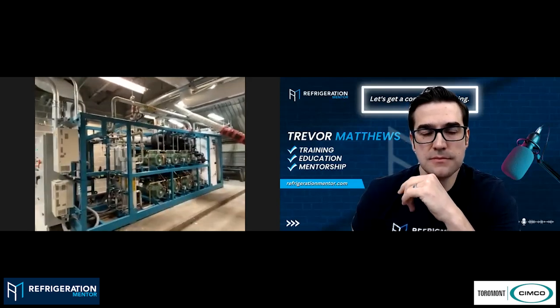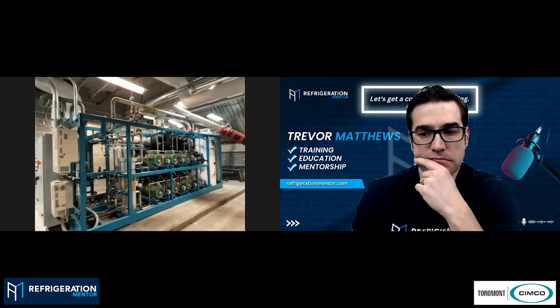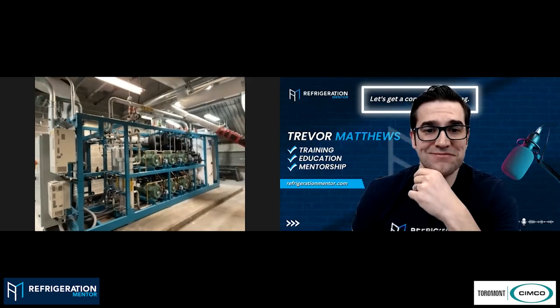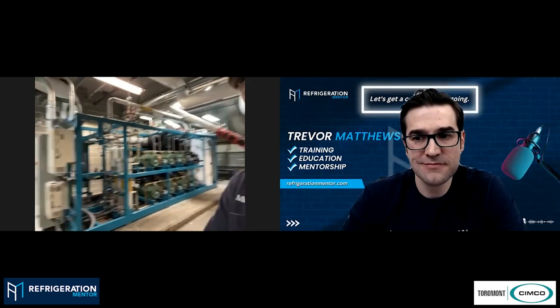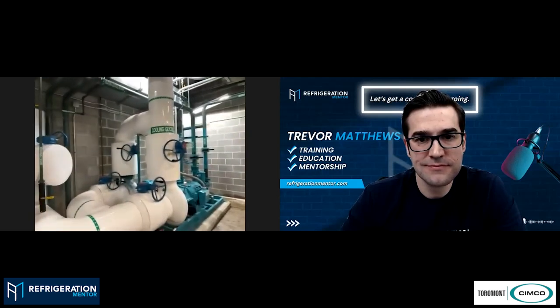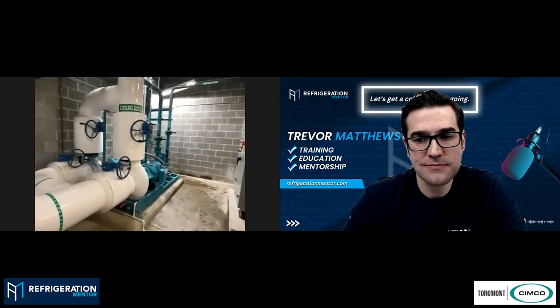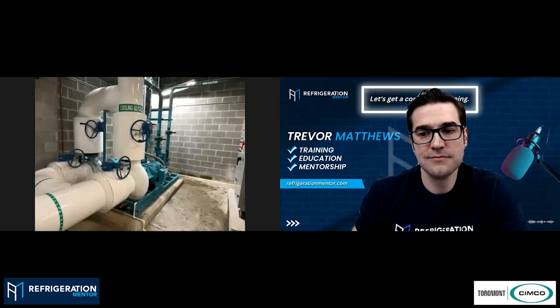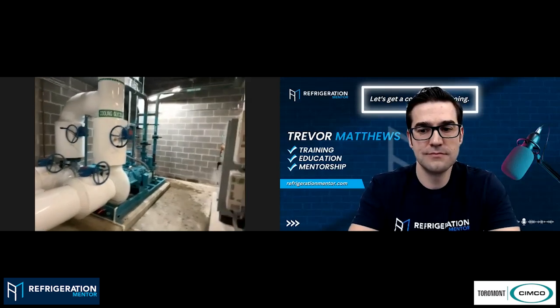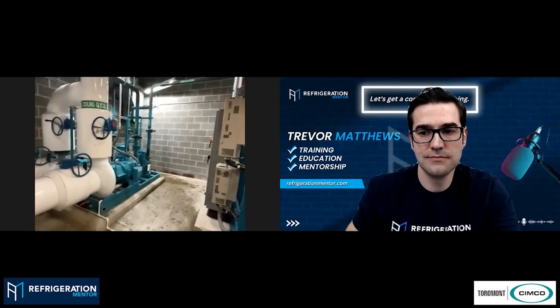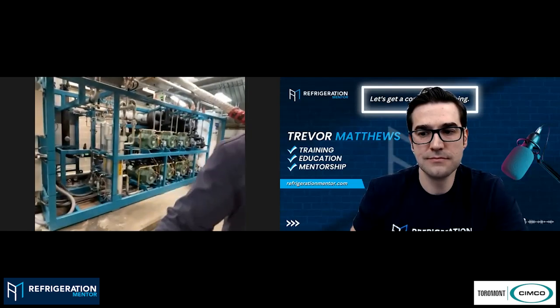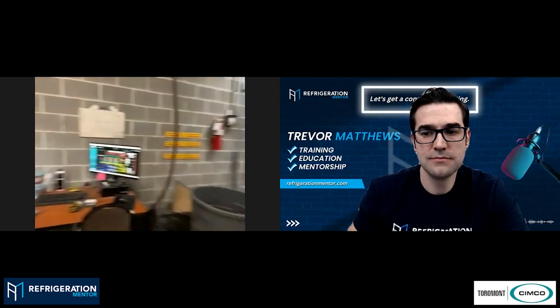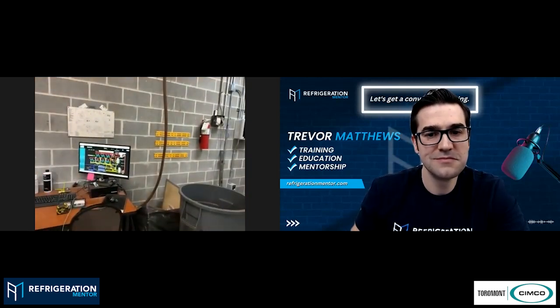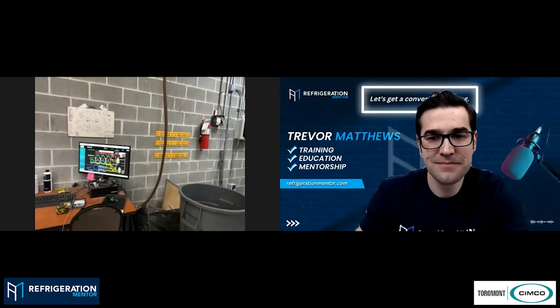The compressors are on the front, and on the backside are the chiller exchangers for the brine as well as the warm glycol. If we step over here, this is our pump skid, where we circulate our chilled brine underneath the floor, as well as our snow melt pit pump and our warm floor pump. And if you step over here, this is our very messy computer desk, but this is our Cimco automation group control system for the rink.